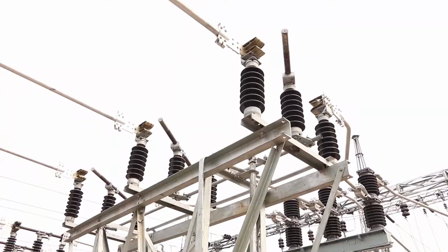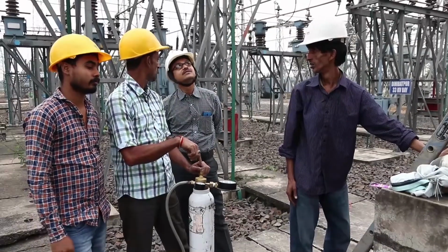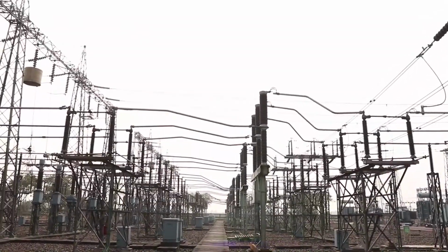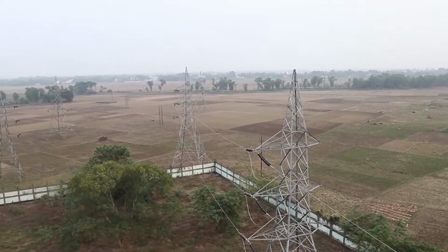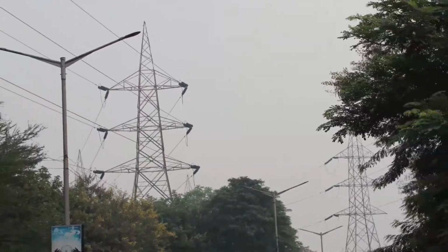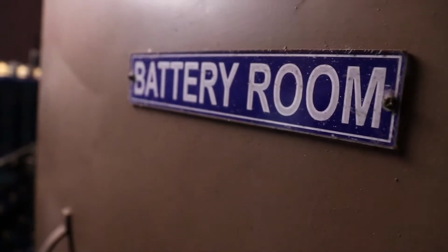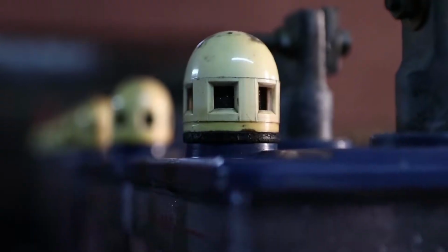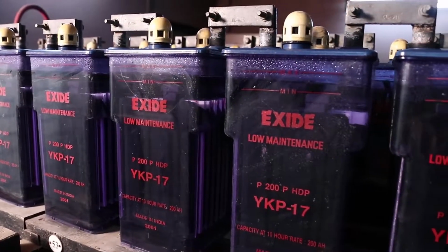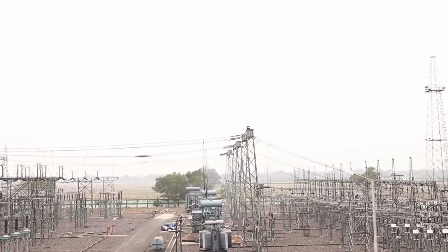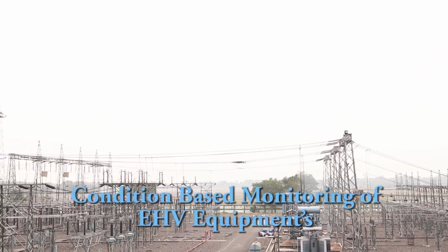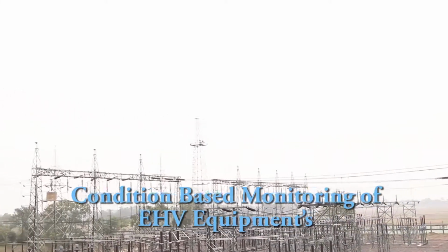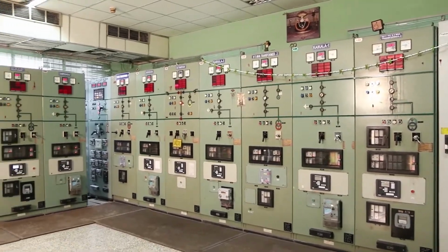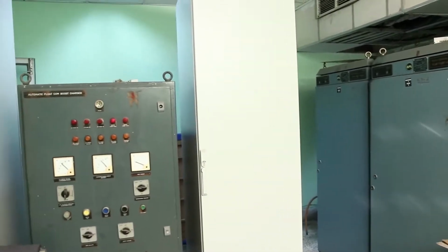Periodic maintenance of all substation equipment, bus, transformer, clamp, connector, etc. is done regularly as per maintenance schedule in order to achieve more reliability and fewer breakdowns. Transmission line patrolling, tree trimming and jumper tightness checking works are also done as per the yearly schedule. The DC systems are maintained at site with timely cleaning, distilled water topping up and specific gravity measurement. As per guideline of WBSETCL, condition-based monitoring of EHV equipment has been adopted with an ultimate aim to reduce operation and maintenance cost and to minimize breakdown.